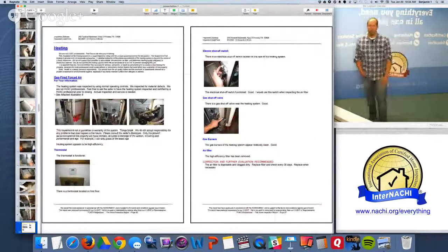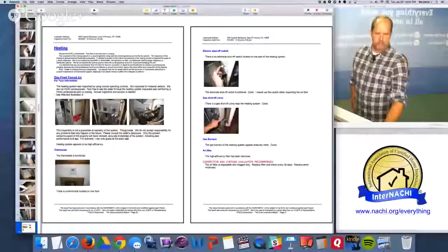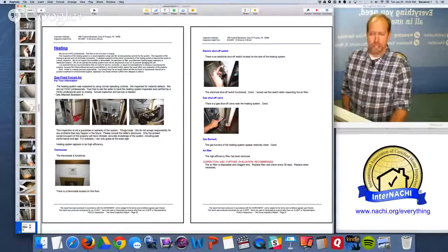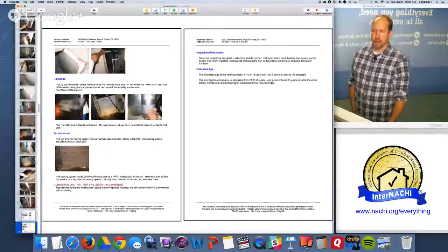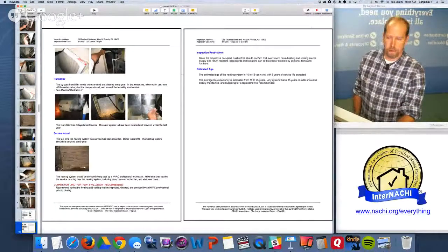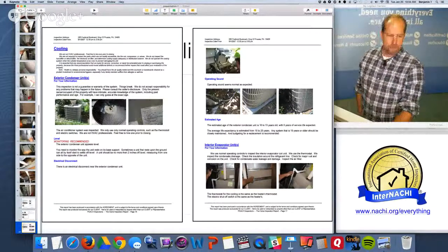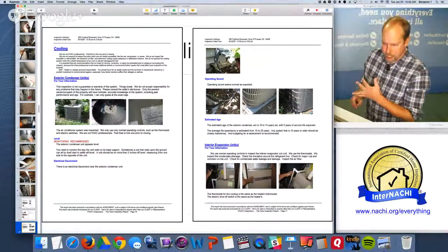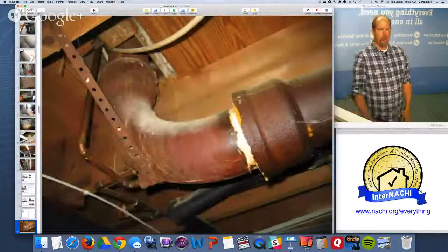In my report I title it 'Heating System.' I identify the system: gas-fired forced air. I describe the heating system and components broken down to the thermostat, electric shutoff switch, gas shutoff, gas burners, air filter — the air filter needs to be attended to — the humidifier, and the service record hasn't been serviced in a long time. Every heating and cooling system needs to be serviced every year. The cooling section breaks down the AC: it's level but needs to be monitored, there's an electric disconnect, the operating sound is normal, estimated age, the interior evaporator unit, and the condensate is handled well. No problems there.